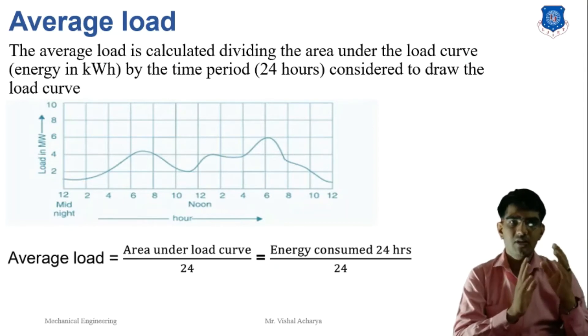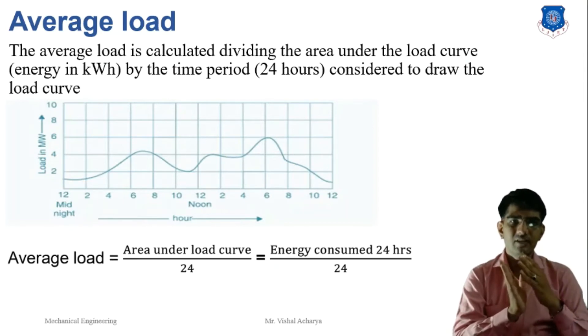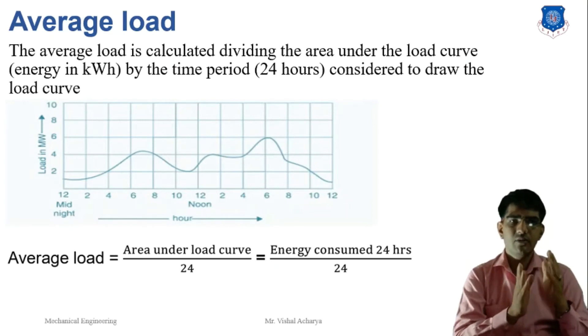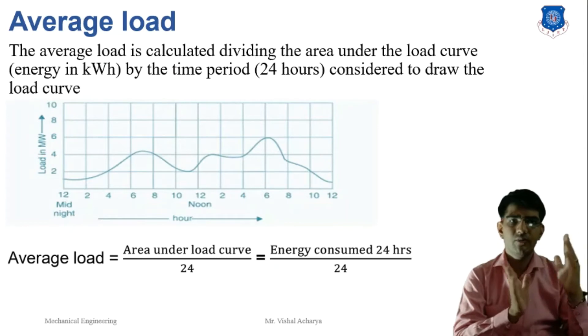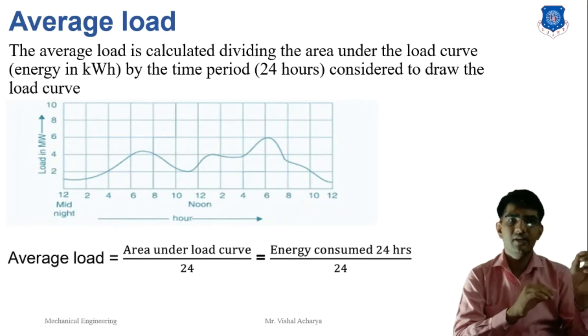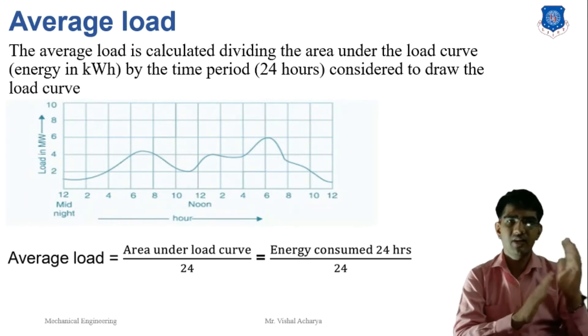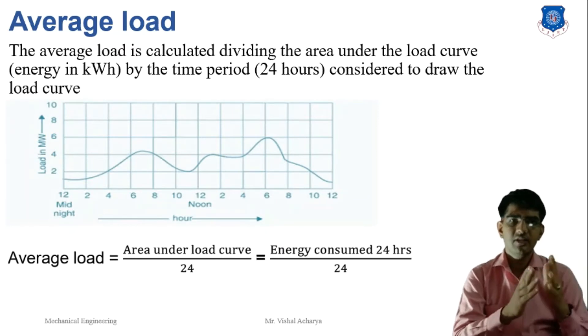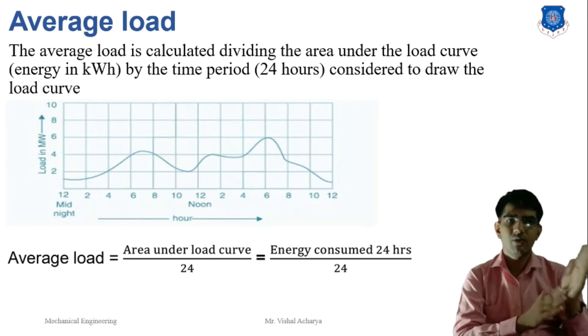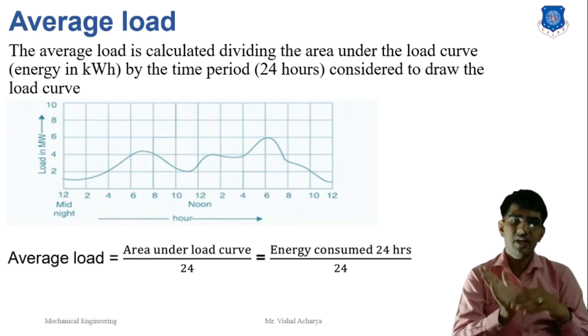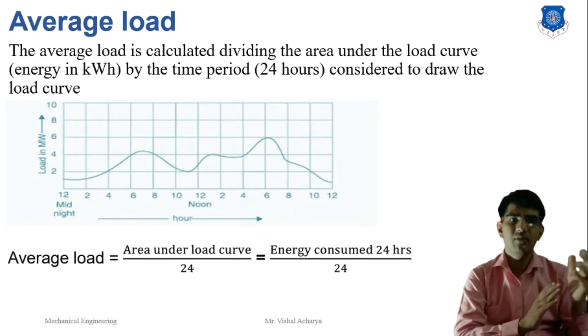If we calculate the average load for a month, the graph presents the load on a day-wise basis. The total area under the load curve for the month divided by 30 × 24 — that is, 720 hours — gives the average load for the month. The same approach applies for calculating the annual average load.